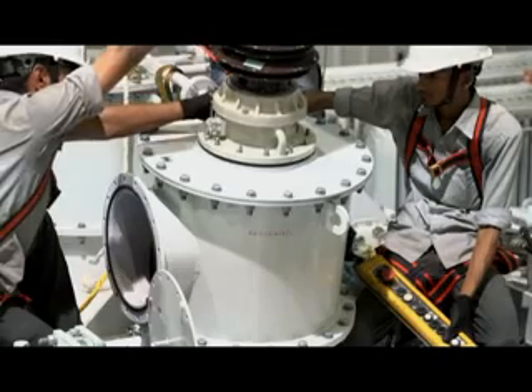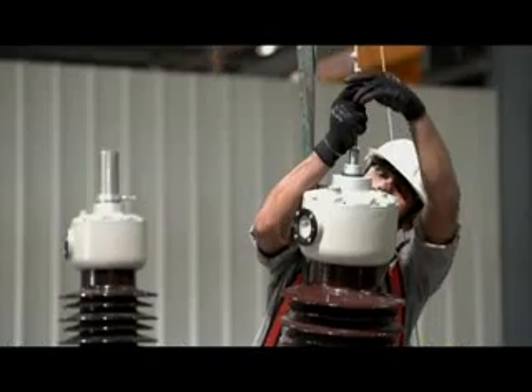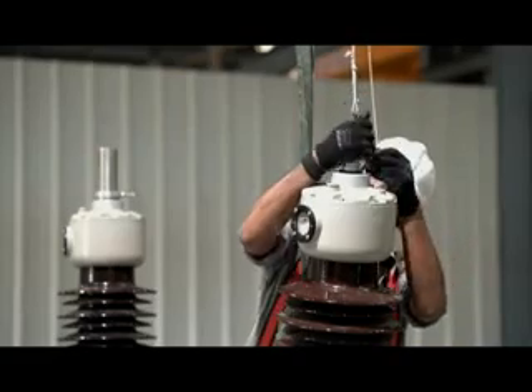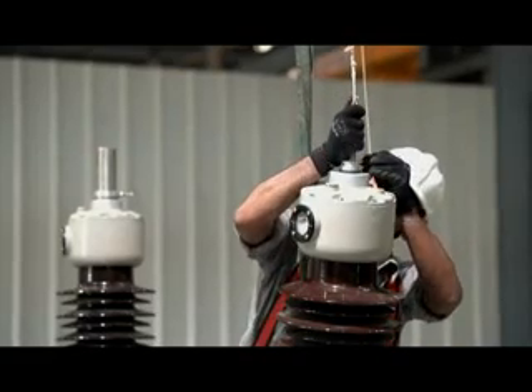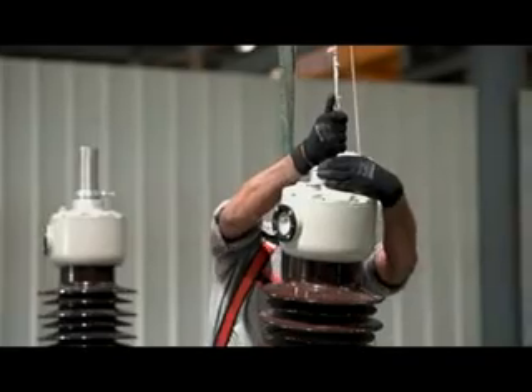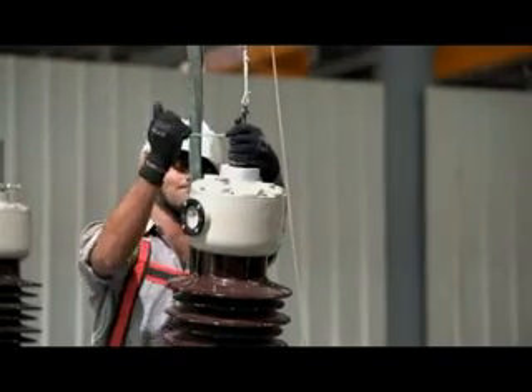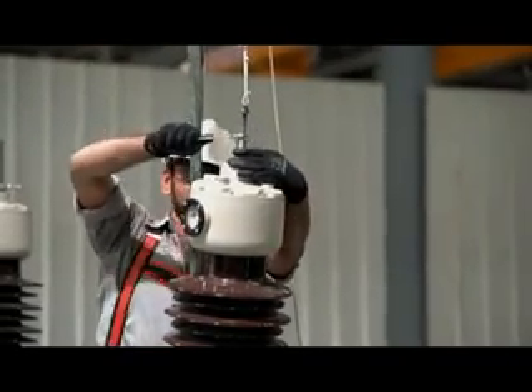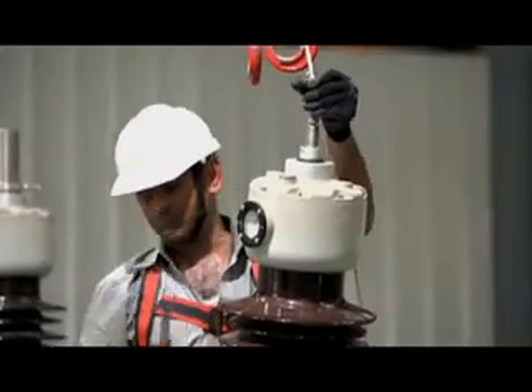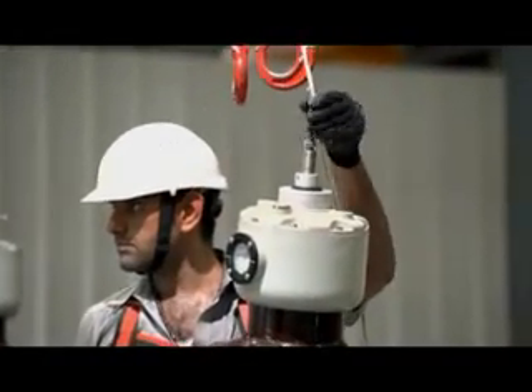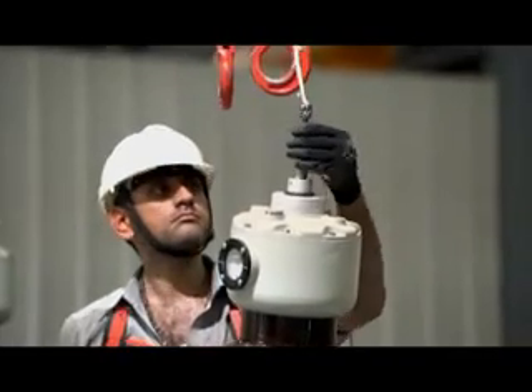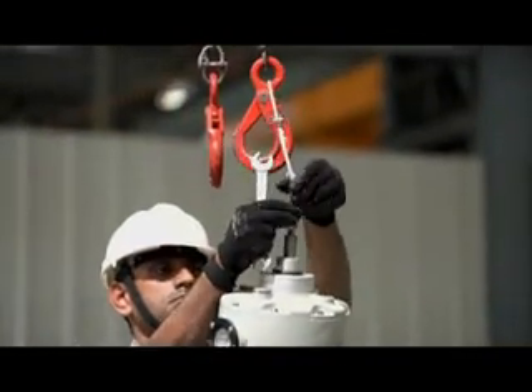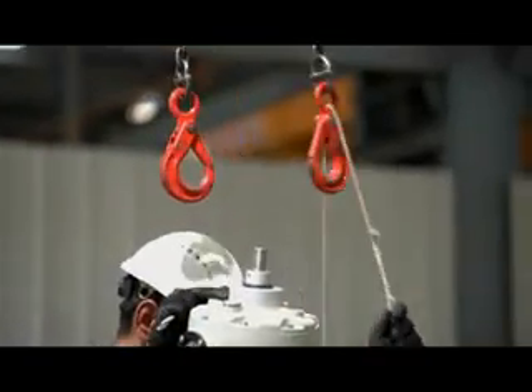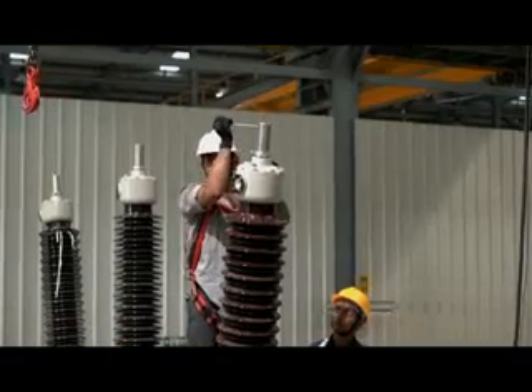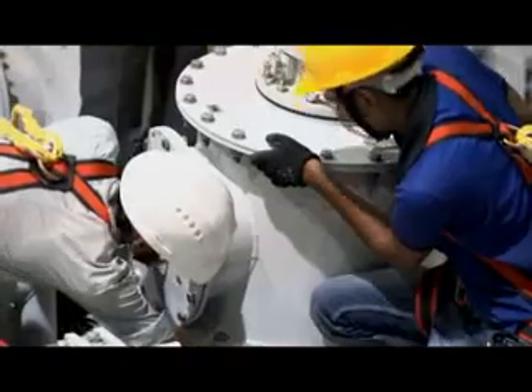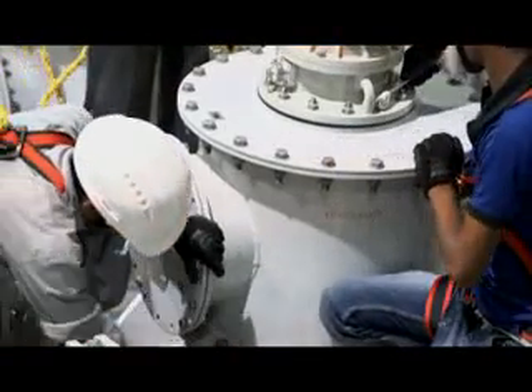The annular space between the condenser body and the housing is filled with pure transformer oil. A disc spring assembly located in the top housing holds all synthetic rubber gaskets and O-rings between porcelain and metal parts under controlled pressure, completely sealing the bushing. An oil sight window is provided on the expansion chamber for observing the oil level. The space in the expansion chamber above the oil is filled with dry nitrogen gas. Due to these hermetic sealings, the bushings are maintained free and non-susceptible to aging.